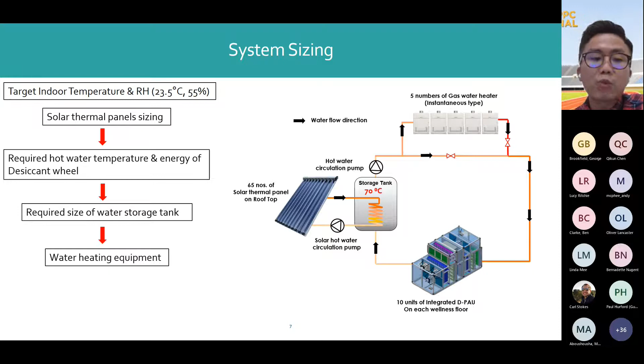Also, the control logic is designed to operate the gas dehumidification system to precisely control the humidity and also the temperature. The gas dehumidification system fully operated in June 2020. A total of 65 solar thermal panels are installed on the rooftop to absorb the solar heat. Then the heat transfers to the water storage tank to heat up the water indirectly. The water heaters will turn on when the water output temperature is below 70 degrees.